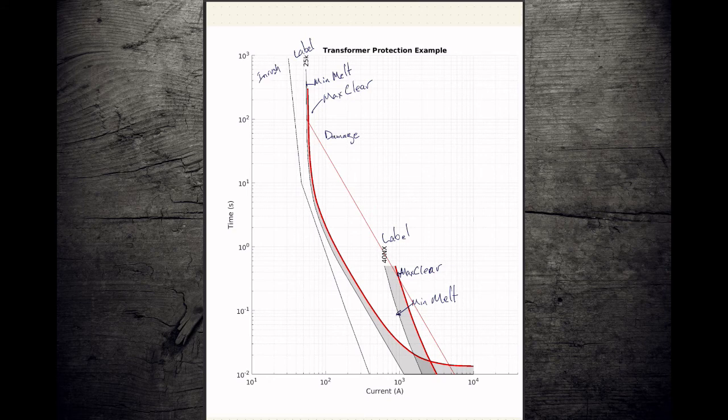The most low-tech option is you can assemble a curve like this by printing out a blank TCC graph, and then the appropriate series families of fuses, and overlaying those, stacking those pieces of paper, and then putting them on either a light box or pushing them up against a window during daylight hours, and you can trace through that top page. You'll be able to see the graphs underneath right through the top page, and you can trace them onto the page.